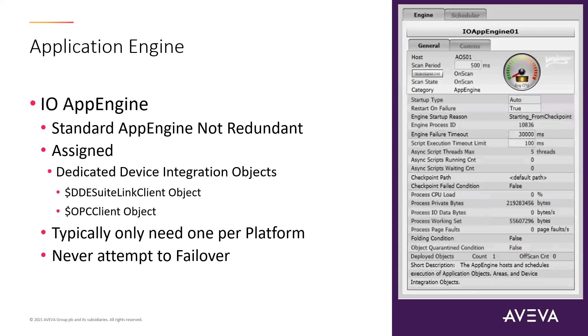Application engines typically include an IO engine responsible for hosting the I/O objects — the dedicated device integration objects, specifically the SuiteLink client object and the OPC client object. Typically only one of these engines is needed per platform, and these objects should not be on a redundant engine because the redundant engine won't take corrective action if they can't communicate. There's a common misconception that the redundant engine will fail over if the I/O doesn't work on a particular node — that's simply not the case. The redundant engine is responsible for keeping the engine operating as a service; it doesn't care if you're getting data from the device.